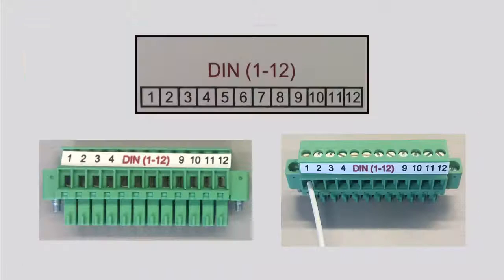Discrete signals only require a single 16 gauge wire. Wire the discrete signal connection from the end device to a numbered digital input terminal labeled DIN on the controller. The number terminal the signal was wired to will correspond to the number channel in the controller. Here we have wired a signal to channel 1.